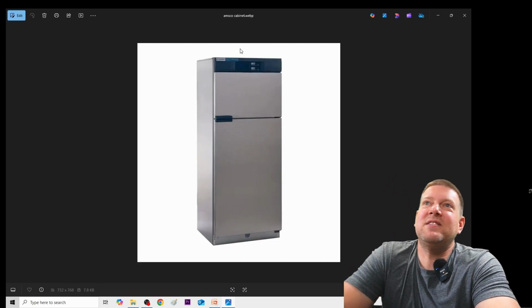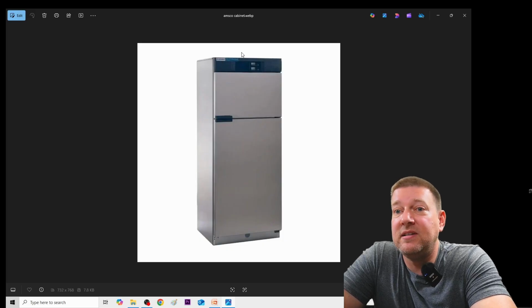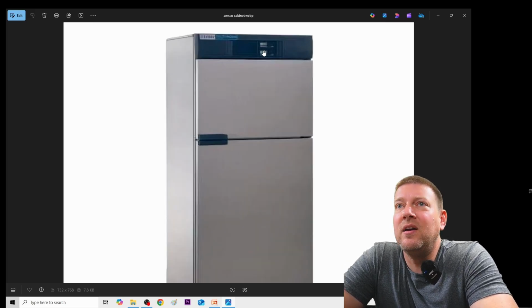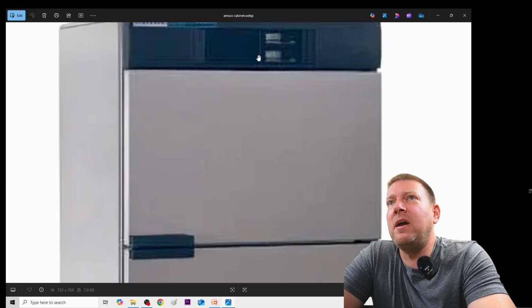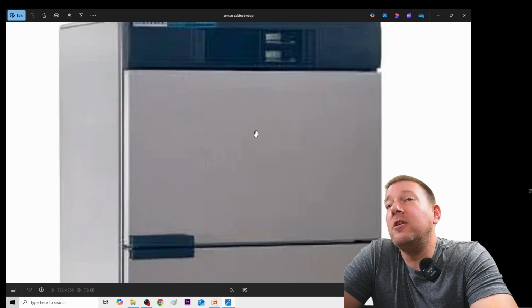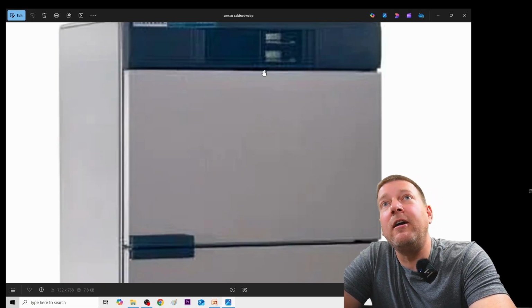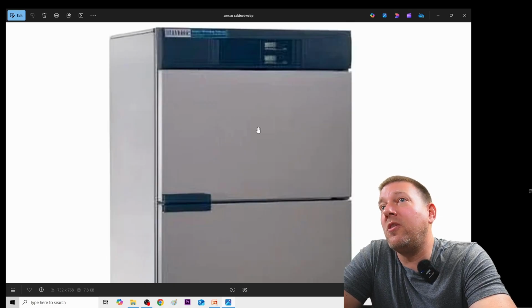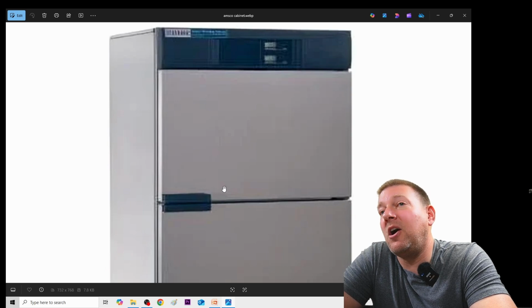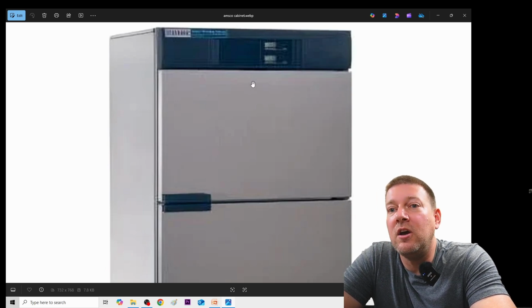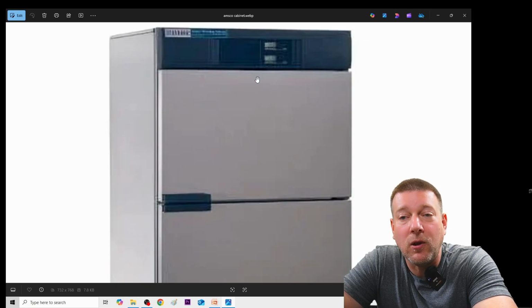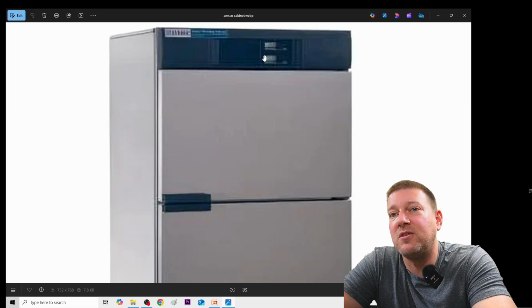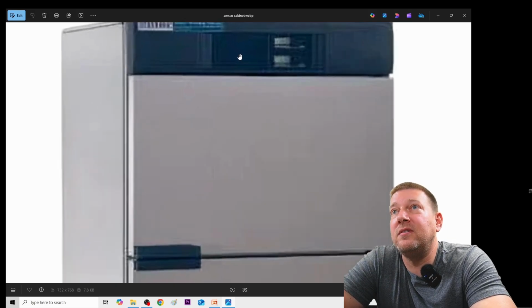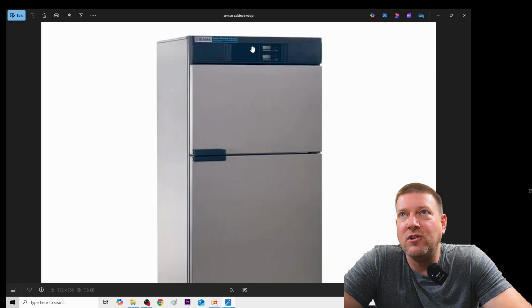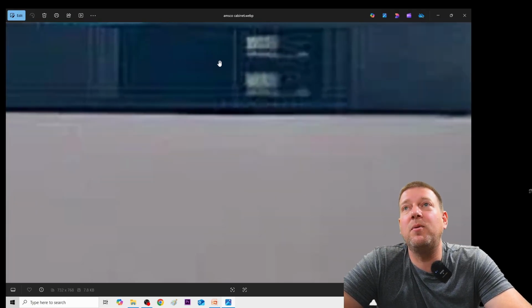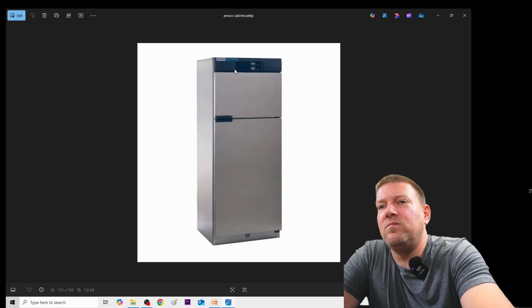Oh, this is going to bring back some memories, guys. Mind you, Gen 2s are still being made to this day. Why? Because if it doesn't need to be more complex, then why make it so? So this guy right here does have a controller, and the power does come in. It does convert it to DC, although some of the functions could be AC, like a heating element. So you have a digital controller that is going to turn on the heating element for both chambers, which the heating element is going to be interrupted by a door detect switch. That could be either AC or DC. It could be an interlock, or it could be a DC signal that just tells the controller, hey, disconnect. It could be either, but this is a Gen 2 product all the way. You have just a little bit of DC stripped off, and then you just have a simple logic controller on this type of thermal cabinet here, Gen 2.